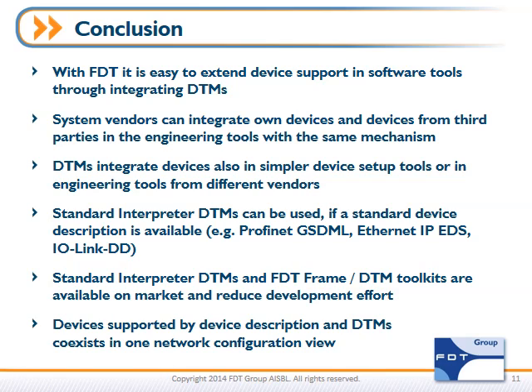If a specific built DTM is not available for a device, it may be possible to use interpreter DTMs. This works for environments like PROFINET with GSDML files, EtherNet/IP with EDS files, IO-Link with DD files, HART with DD files, and so on. There are standard interpreter DTMs, toolkits for building frame applications, and toolkits for building DTMs available on the open market. These tools reduce development efforts by not requiring developers to start from the ground up to be compatible with the FDT standard. Devices supported by device descriptions and full-featured DTMs can easily coexist in a single network configuration view.